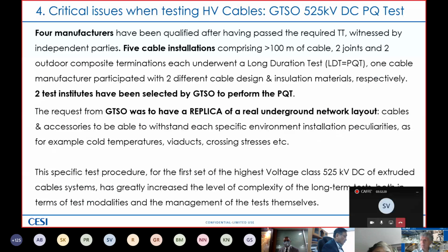Talking about this project, 4 manufacturers have been qualified after having passed the required type test, witnessed by independent parties. 5 cable installations, each comprising more than 100 meters of cable, 2 joints and 2 outdoor composite terminations, underwent a long duration test. We are used to calling it the pre-qualification test. Why 5 cable installations? Because one cable manufacturer participated with 2 different cable designs and insulation materials, respectively. 2 test institutes were selected by the German TSO to perform the pre-qualification test. One was KEMA Labs, and the other was a second institute.